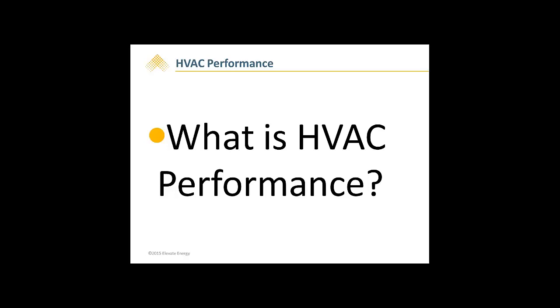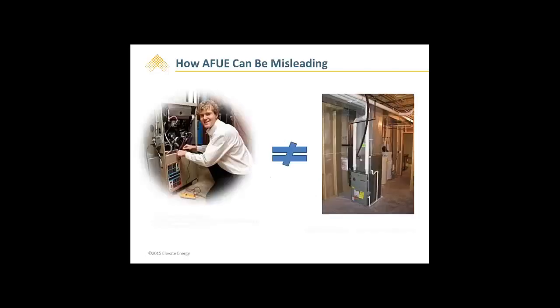So HVAC performance shifts the evaluation of efficiency from out of the box, as determined by a handful of engineers in a lab environment with nothing attached to the furnace, to installed and operating, as that specific box is performing within a specific system. In fact, the fundamental principle of HVAC performance and the HVAC SAVE program is that operating efficiency is a far better measure of true efficiency since it is measured and not deemed. Furnace AFUE is determined by engineers in a lab, while HVAC performance measures everything added to the furnace in the field.